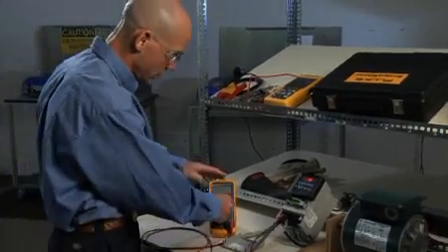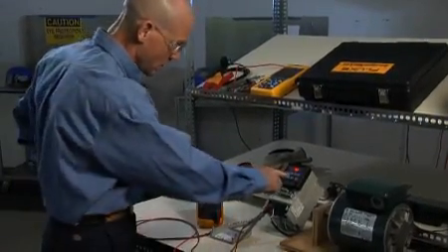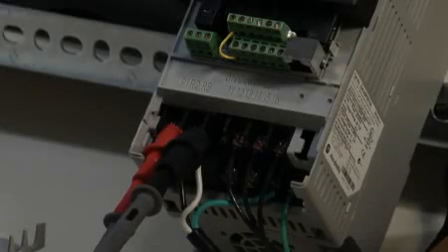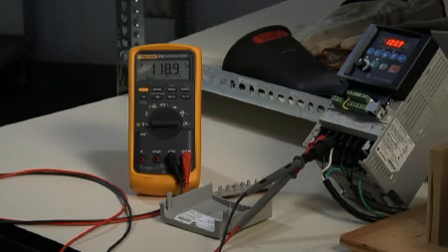With a digital multimeter, we can check the line input voltage. But depending on the type of distortion, the peak value may not reveal whether a problem exists. When we check the VSD DC bus voltage, we find that it's about 20% under the nominal value. That's a problem.